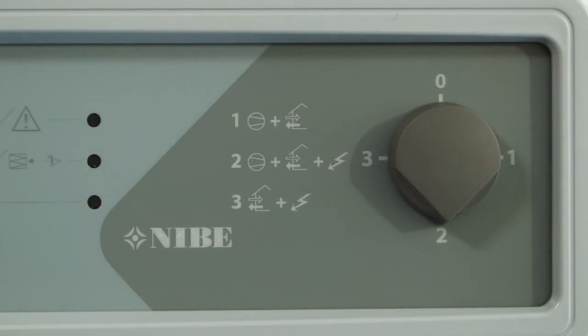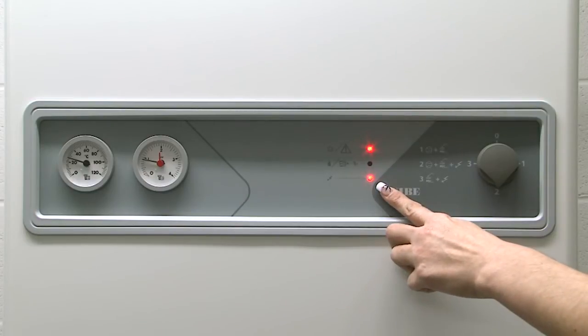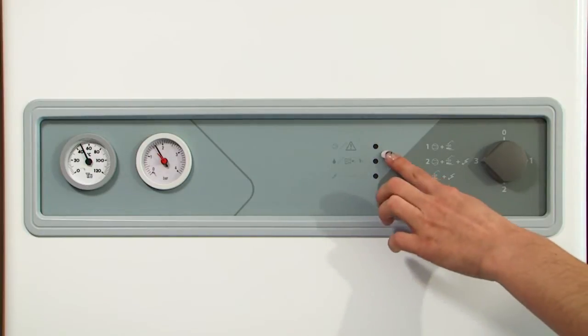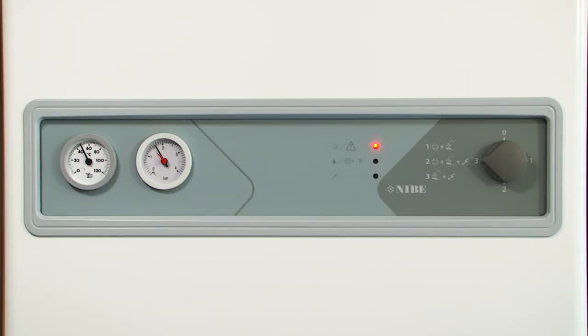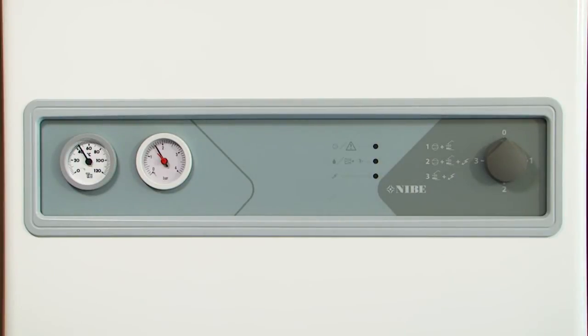Number two on the control knob is referred to as winter mode and is to be used during the colder months of the year. This setting gives permission for the heat pump to use its built-in immersion heater when the pump needs to generate more heat. Number three on the control panel is referred to as rescue mode and is only to be used in an emergency when you have been advised to switch to it by a qualified engineer or Nibe themselves. In this demonstration the top light is flashing, which is normal for setting three, simply indicating that the heat pump is now in rescue mode and will rely on providing heating and hot water from the built-in immersion heater only. Should you need to disengage this operation, turn the unit back to zero and leave it for around 20 seconds to reset, then turn it back to number one to resume normal operation.